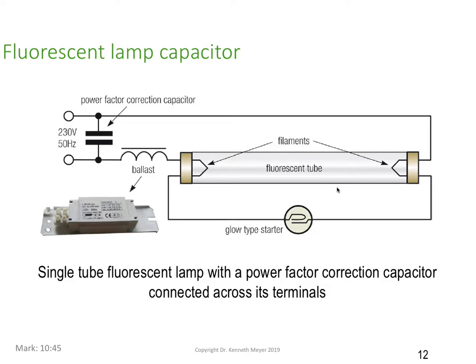Now, the difficulty is, with a fluorescent tube, once the gas has actually ignited and is conducting electricity, it goes from being highly insulative to being highly conductive. In other words, the resistance of the gas drops dramatically. So we have to put something in the circuit which is going to restrict the current. And along comes our friend the ballast that does that. So the ballast restricts the current and allows the right amount of current to flow through the gas in the tube to give us the light. The difficulty, of course, is that this is an inductor. It's just a coil of wire wrapped around a steel core, and it's highly inductive.